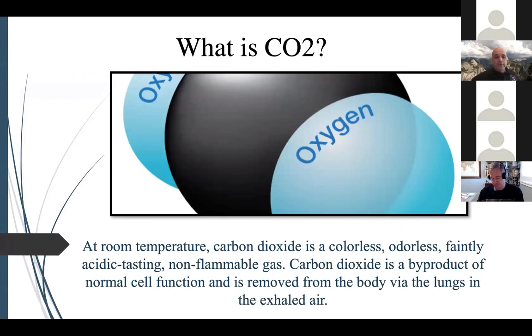So what is CO2? We all exhale CO2, it's carbon dioxide, about 2.3 pounds of it a day. Because we exhale so much of it, having a good CO2 meter allows us to use that as a metric, a way to validate a building is getting enough ventilation. If we're breathing out quite a bit of carbon dioxide and it's building up in a room, that's an indicator there's not enough ventilation.